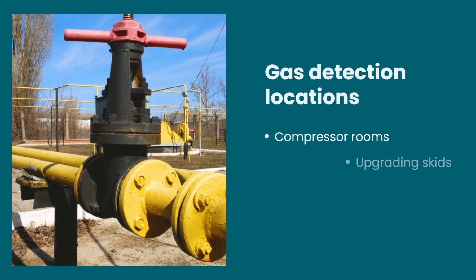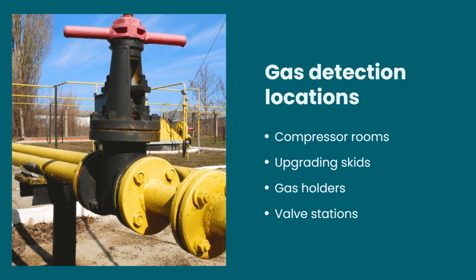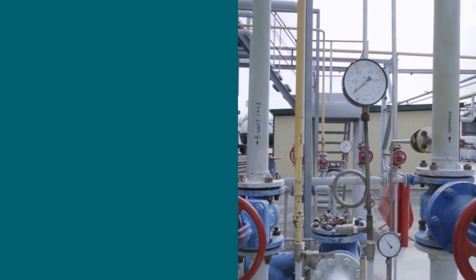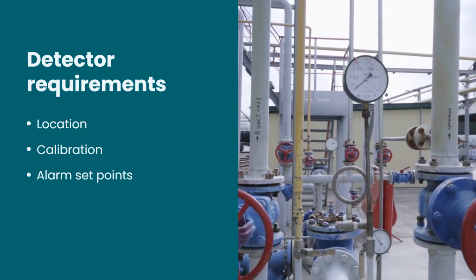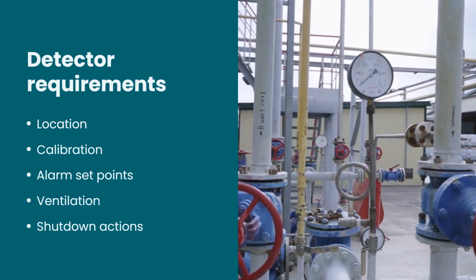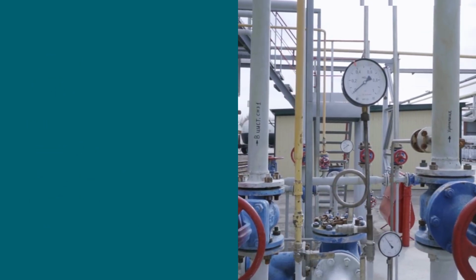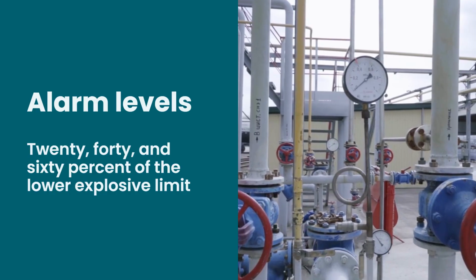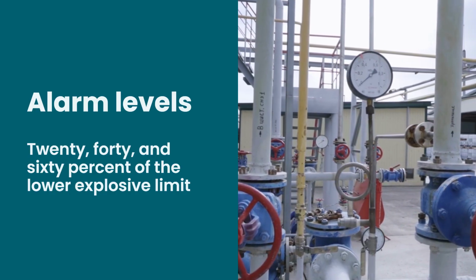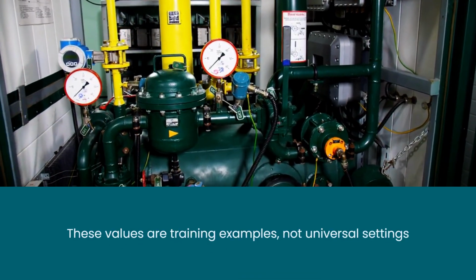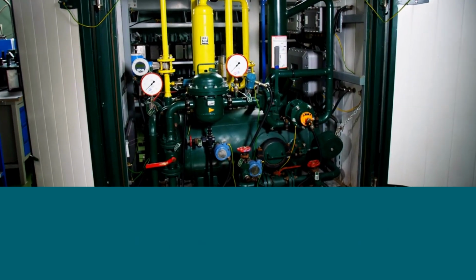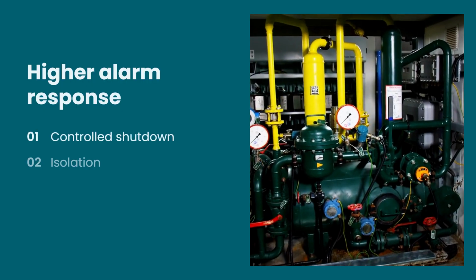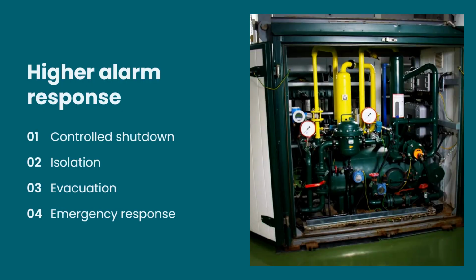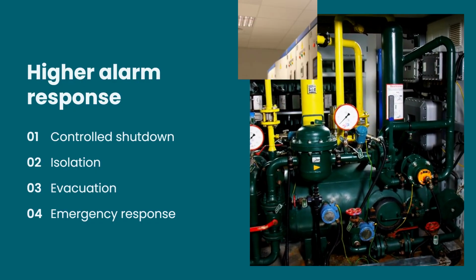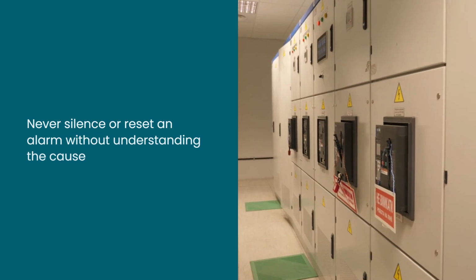Fixed gas detectors may be installed near compressor rooms, upgrading skids, gas holders, and valve stations. Detector location, calibration, alarm set points, ventilation, and shutdown actions must follow the approved design. Some facilities use staged methane alarms at 20, 40, and 60% of the lower explosive limit. These values are training examples, not universal settings. Follow the plant's approved alarm philosophy. At higher alarm levels, the process may require controlled shutdown, isolation, evacuation, and emergency response. Never silence or reset an alarm without understanding the cause.